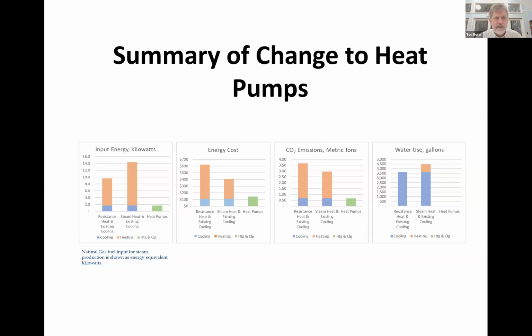I'll skip this, but suffice it to say, by moving to this system we save a huge amount of electricity, a significant amount of energy, and a lot of CO2. By not running cooling towers, we avoid evaporating 50 to 80 million gallons of potable water each year. If we were doing this project in Baja California, New Mexico, Atlanta, or Arizona, we'd do the same project but be celebrating how much water we were saving. And incidentally, we also saved a lot of money and a lot of carbon footprint. So this technology is very much a water-saving as well as an energy-saving technology, with the heat pumps, geoexchange, and thermal storage.